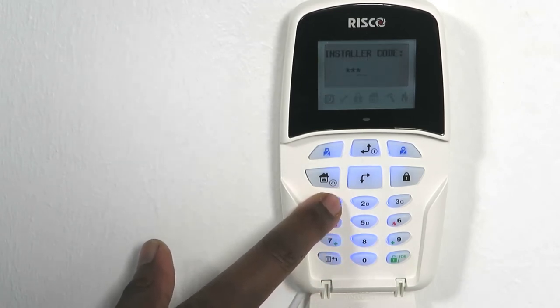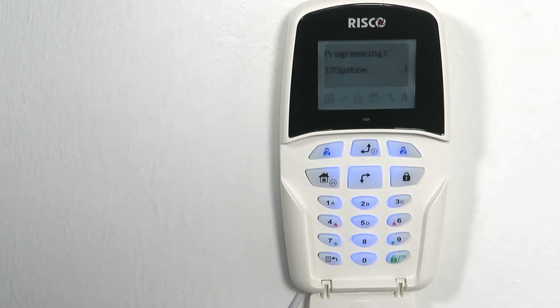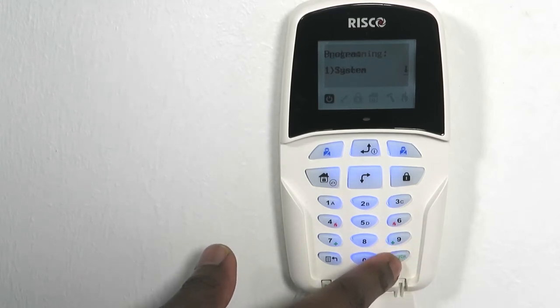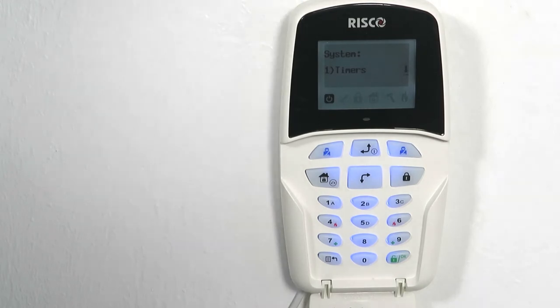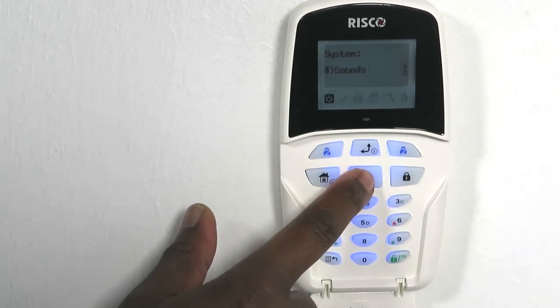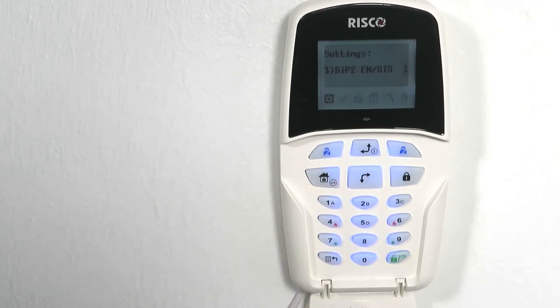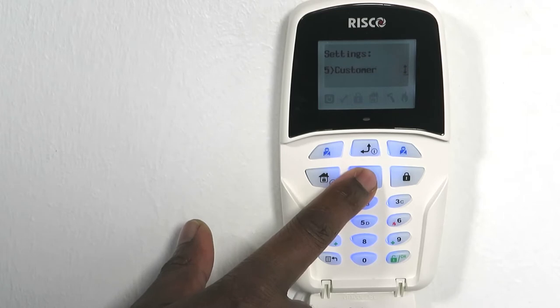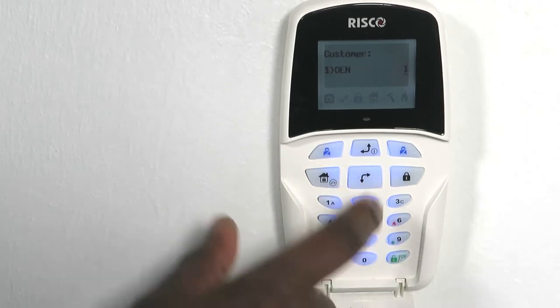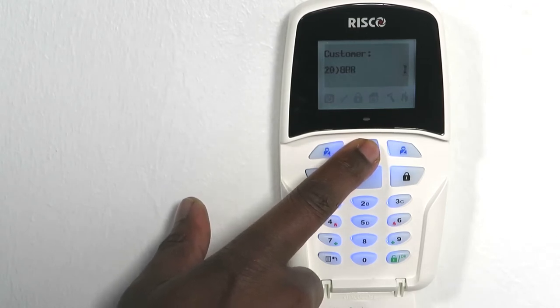Set the customer profile on the panel to 0UL before programming any zones or partitions, as this defaults the panel. To do this, press the menu button and enter 1111 followed by OK. Press OK to select System. Scroll down to Settings using the scroll button and press OK. Scroll down again until you reach Customer and press OK to select it. Scroll up to 0UL and select it by pressing OK.